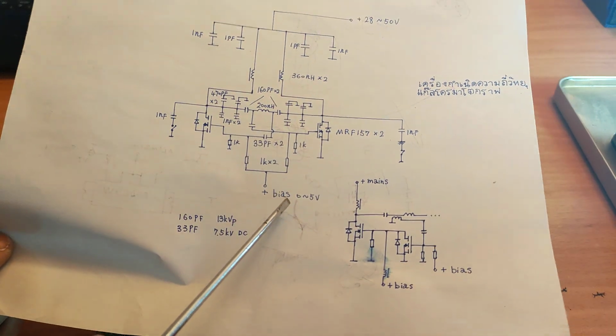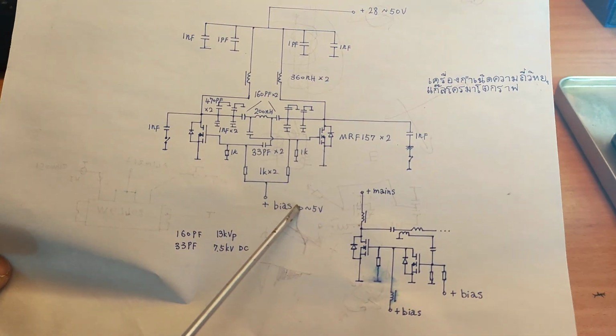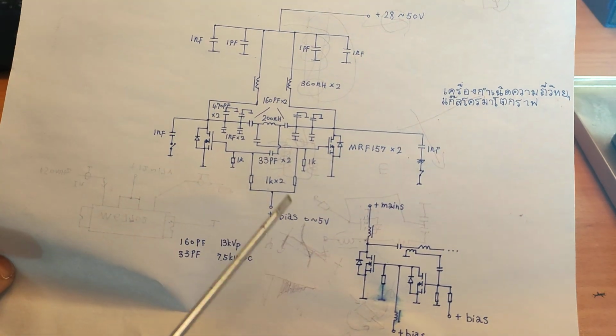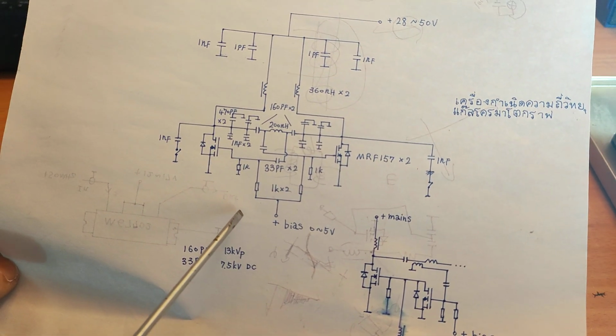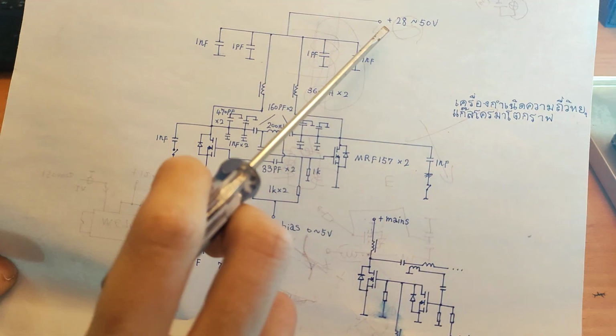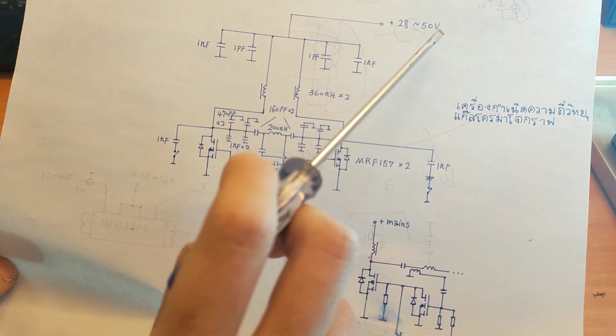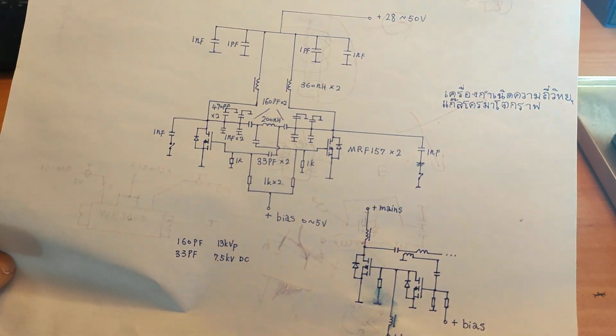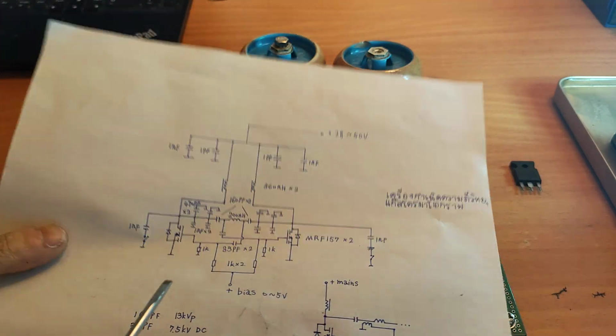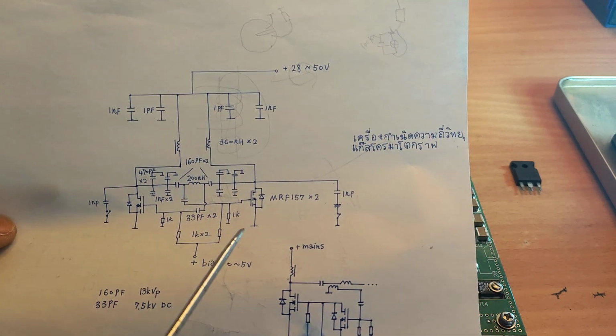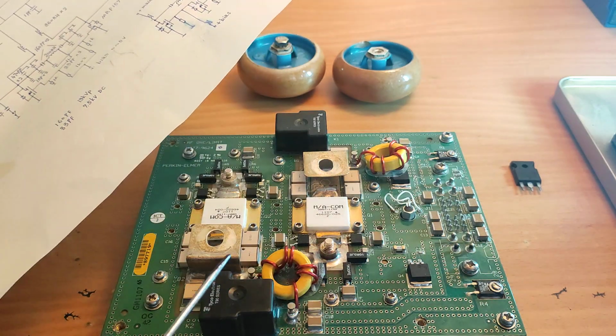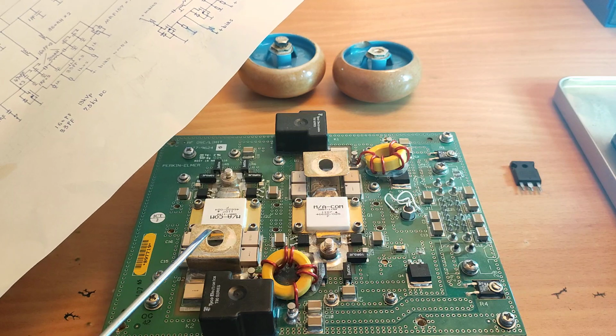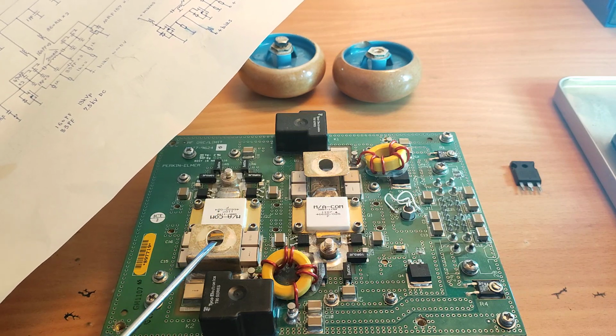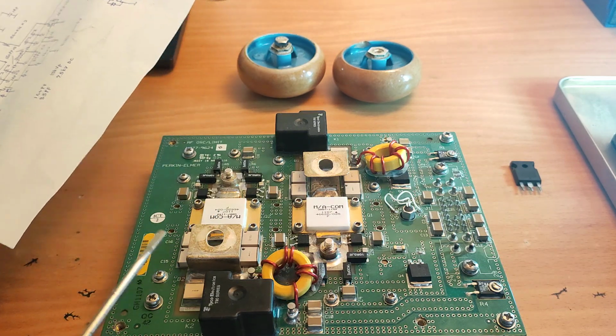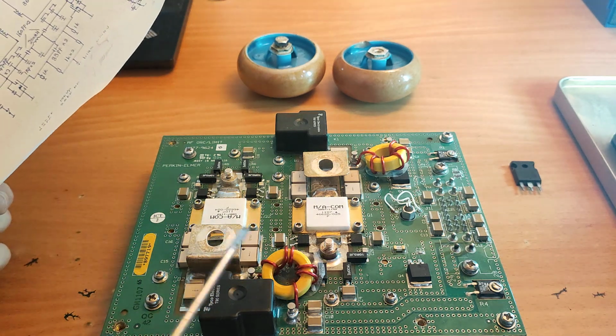Also, the bias is controlled by the microprocessor in that equipment, the ICP-OES equipment. The plus supply is regulated by the microprocessor as well. In the document PDF, the manufacturer says that they can vary the RF power from 500 watts to 2300 watts with an accuracy of 1 watt.